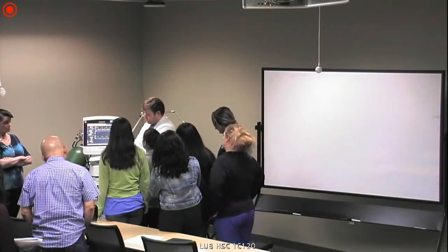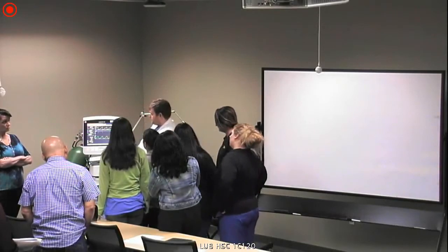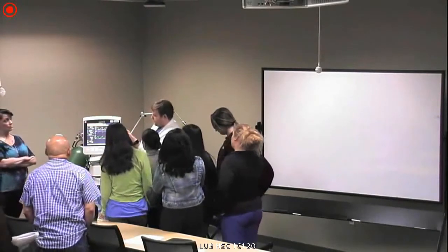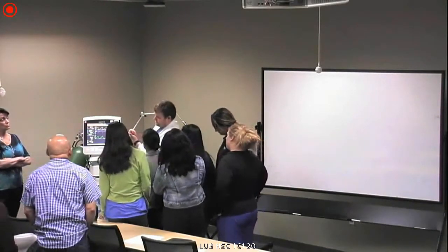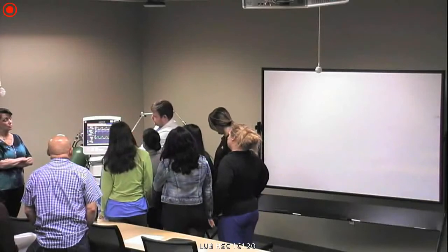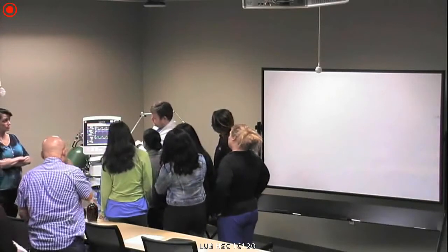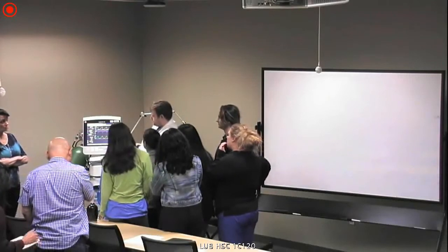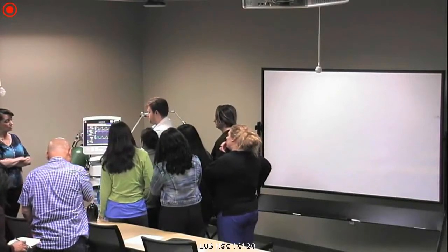The problem is if you really have an obstructive lung disease, you have to allow for exhale time. Normally, you're going to have resistance coming from the airways. So it's really just kind of giving this resistance. So you can see something more like this.